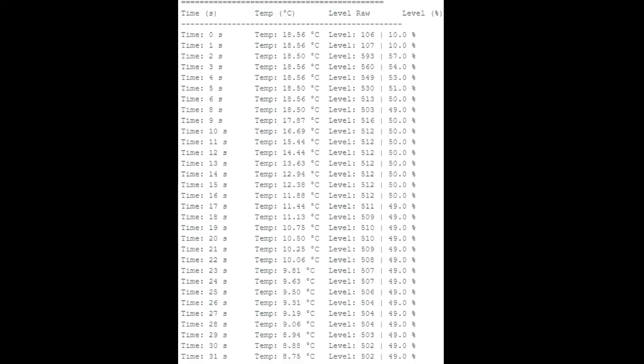As seen by the results here, when the sensors are exposed to the ambient air, the temperature is 18.56 degrees Celsius and the level is 10%. But as the sensors are both submerged at about 2 seconds, you can see that the level immediately jumps up to about 57%, and the temperature slowly declines as observed after 31 seconds of being in the ice water.